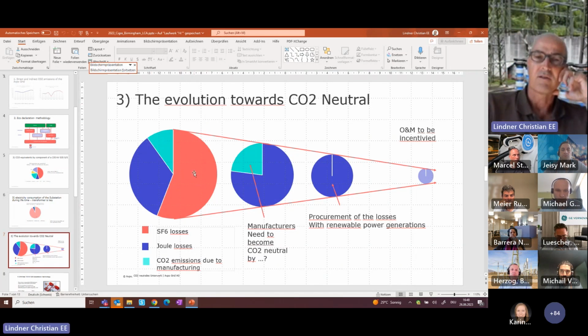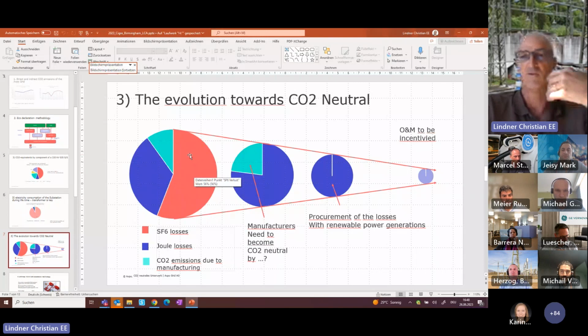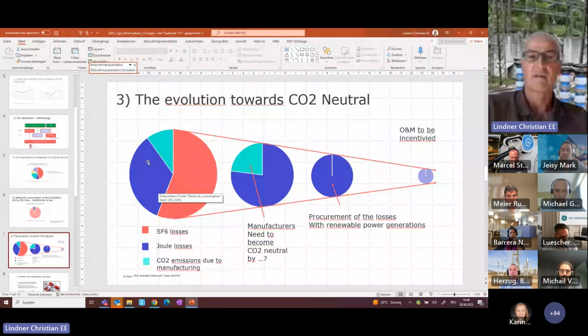The major part of the CO2 footprint on the substation is due to SF6 losses. So more than 50% of your CO2 footprint of a high voltage substation comes from SF6 losses, considering a leakage rate of 0.1% per year. Then the other part is Joule losses, and then manufacturing losses.